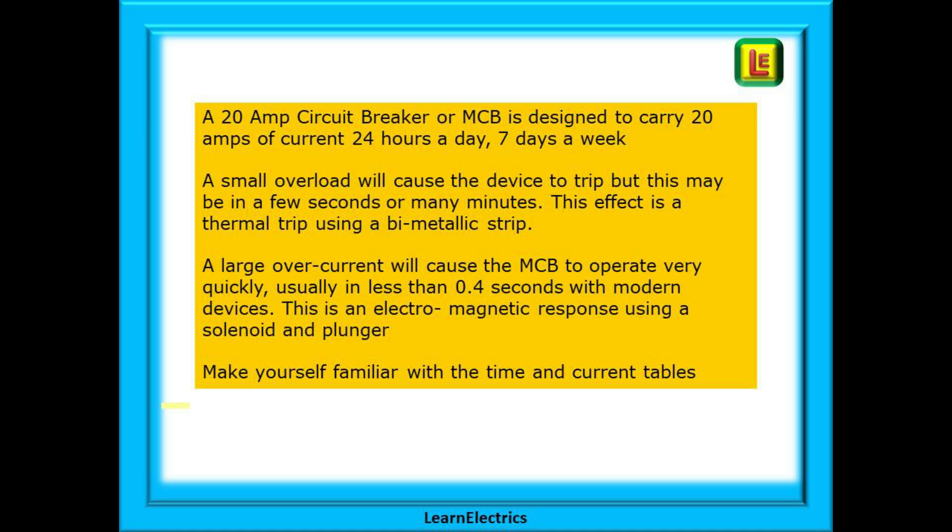This effect is a thermal trip using a bimetallic strip. But a large overcurrent will cause the MCB to operate very quickly, usually in less than 0.4 seconds with modern devices. This is an electromagnetic response and uses a solenoid and plunger.